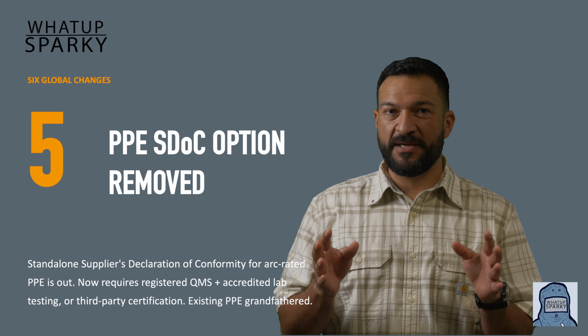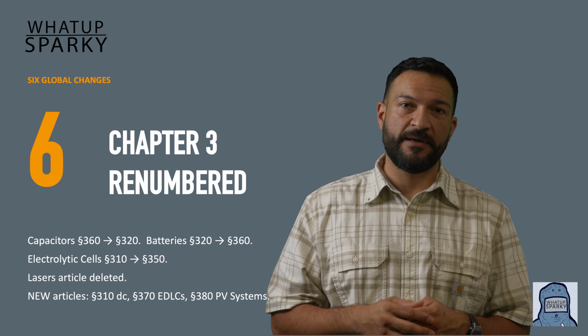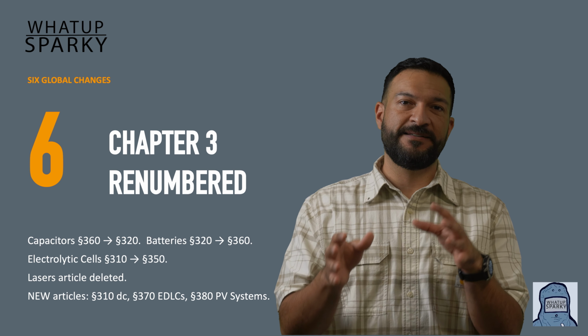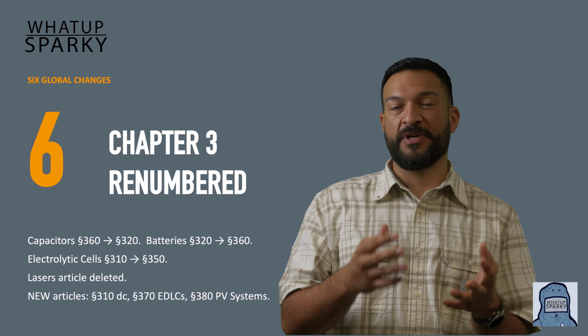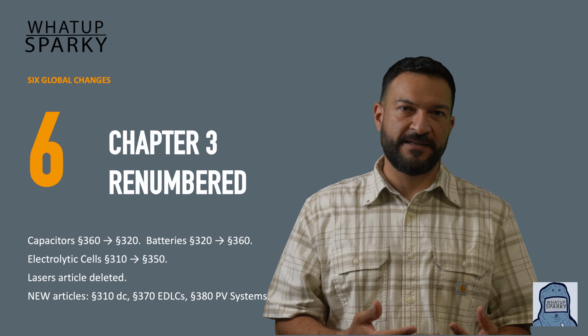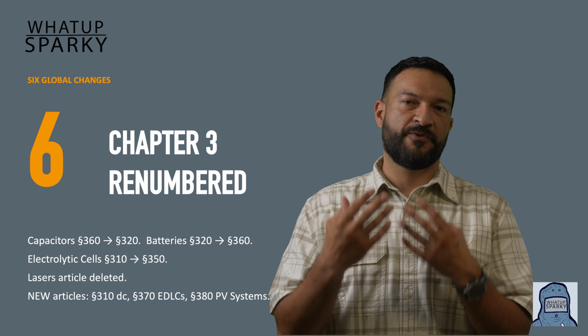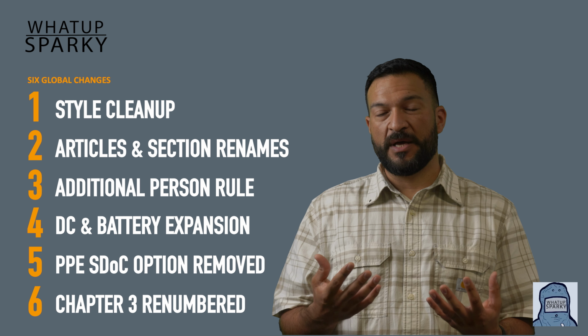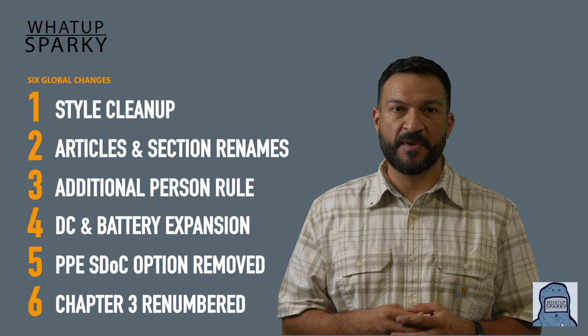Six, Chapter 3, special equipment, had some renumbering. Capacitors moved from Article 360 to Article 320. Batteries moved from 320 to 360. Electrolytic cells moved from 310 to 350, and lasers got removed entirely. We got three new articles: DC hazards, EDLCs, and the brand new Article 380 for photovoltaic systems. Most of the cycle's energy went into those six categories. Remember, the style manual updates basically touch every article. The technical changes cluster around DC systems, battery work, and the energized work permit framework.